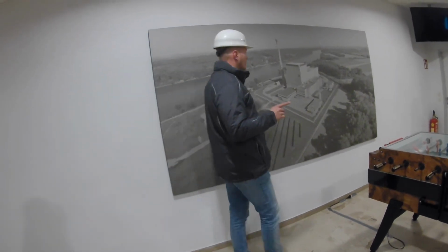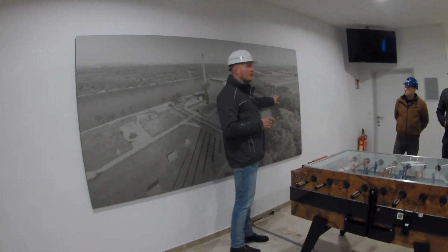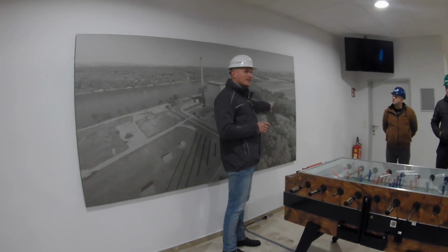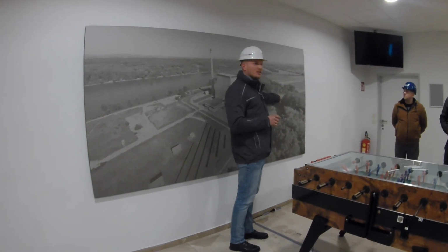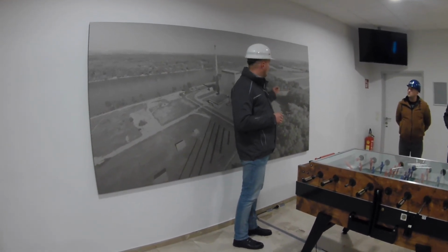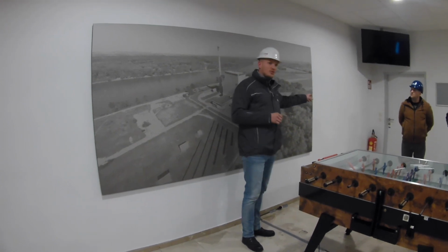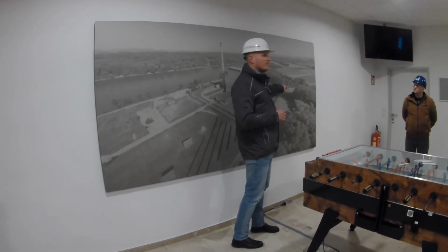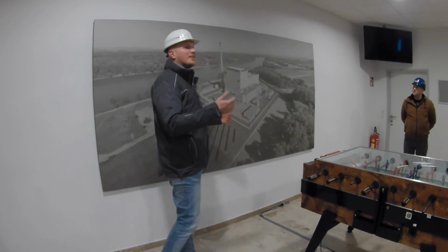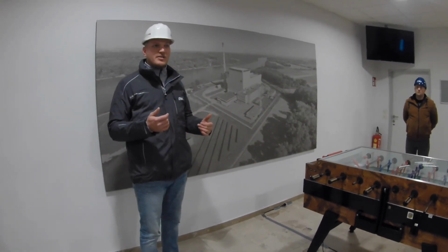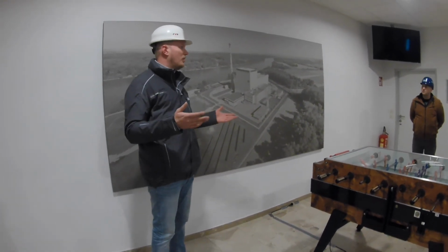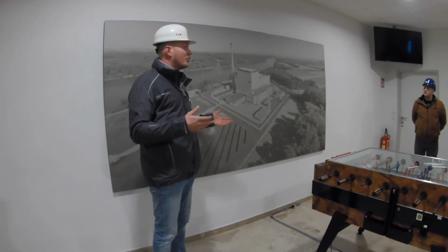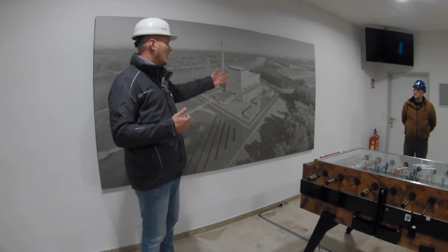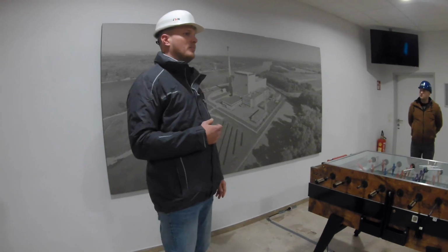One thing I forgot - we have 2 high voltage lines. There is the higher, bigger one, 220 kilovolts, to feed the produced power to the grid. And then there is the smaller one, 110 kilovolts, to get power from the grid during maintenance. Of course, a nuclear power plant which is not in operation still consumes a lot of power, therefore we have the second high voltage line.